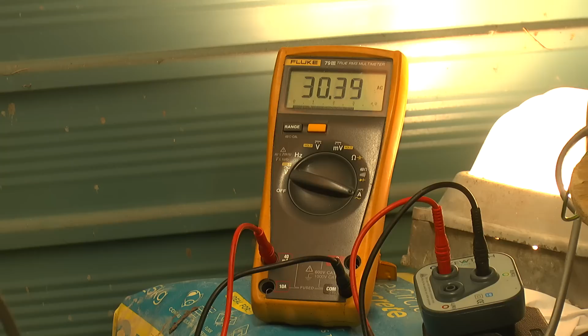In any case, the supply for this is supposed to be, according to the manual, single pole protected. You don't want a double pole RCD on it if it's running as a UPS - apparently it does not like it. The neutral needs to be referenced back through the main supply to earth.